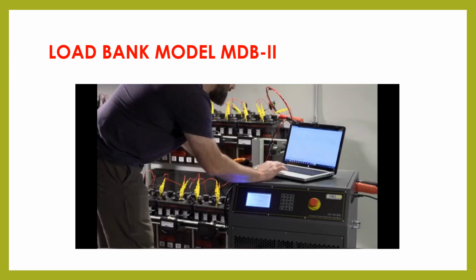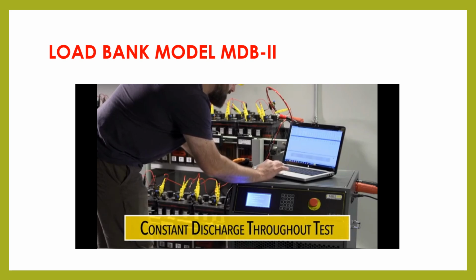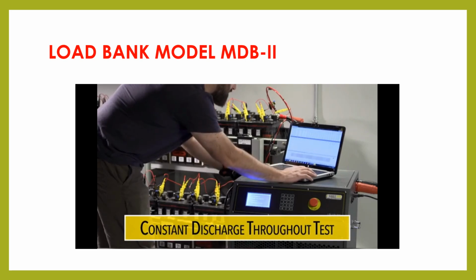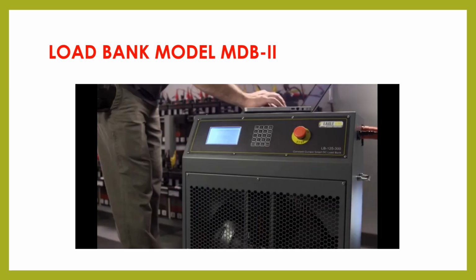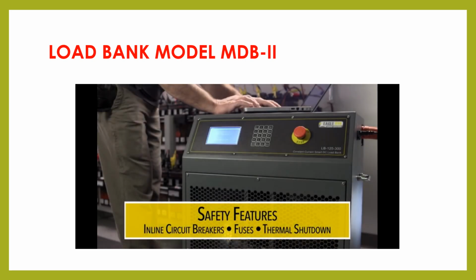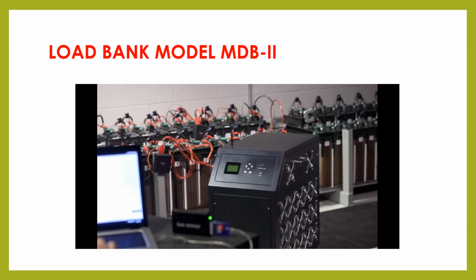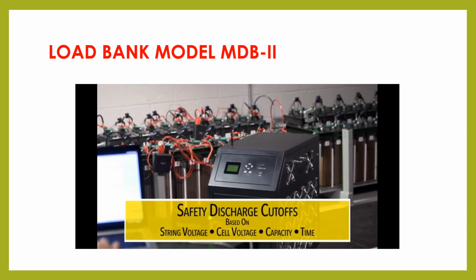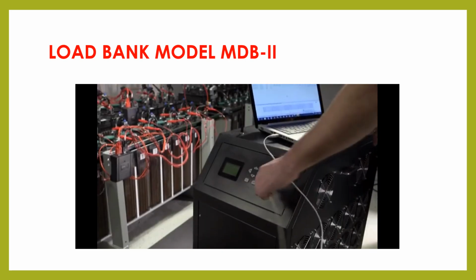Our smart load banks maintain constant discharge throughout the entire test without manual adjustments. We offer many safety features like inline circuit breakers, fuses, and thermal shutdown. Each unit includes adjustable safety discharge cutoffs based on string voltage, cell voltage, capacity, and time. While load testing is critical, it doesn't have to be cumbersome.